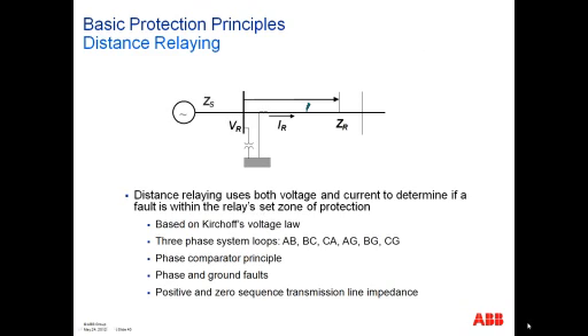Distance relaying is often referred to as impedance relaying, but it's being able to measure the impedance to the fault and making a decision whether that's within its zone characteristic or not. The three-phase system loops are the AB, the BC, the CA loop, but also the A to ground loop, B to ground loop, and C to ground loop. And you have a phase comparator principle that generally is used to determine whether the fault is within the zone or external to the zone. You're able to detect both phase and ground faults, and utilize both the positive and zero sequence transmission line impedances to do so.